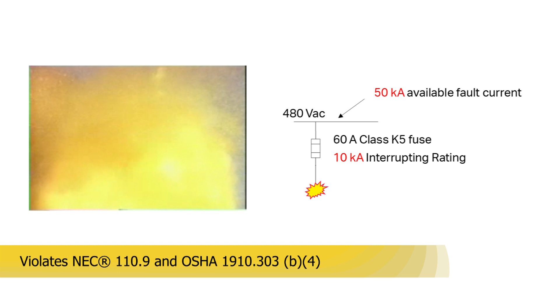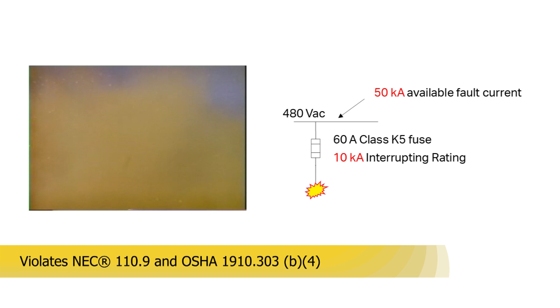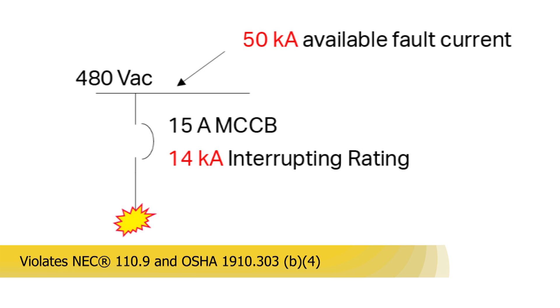Notice the large destructive forces released during the test. This presents a serious safety hazard and misapplication. The next test shows a higher rated circuit breaker on the same test circuit with a short circuit directly on the load side of the two-pole device.